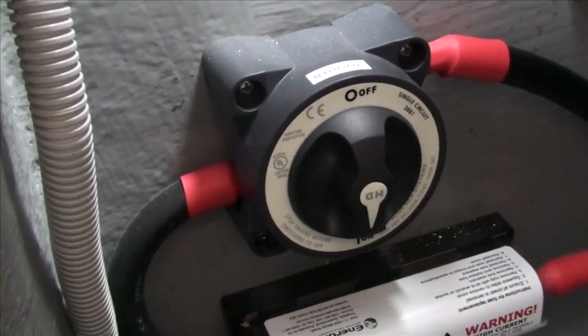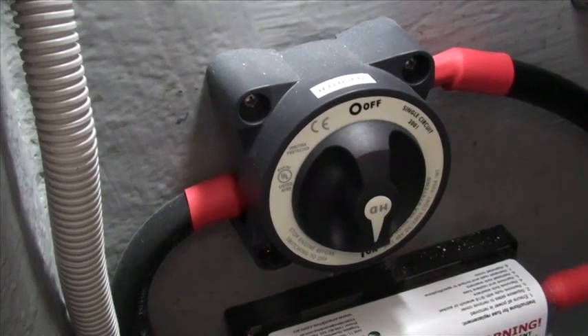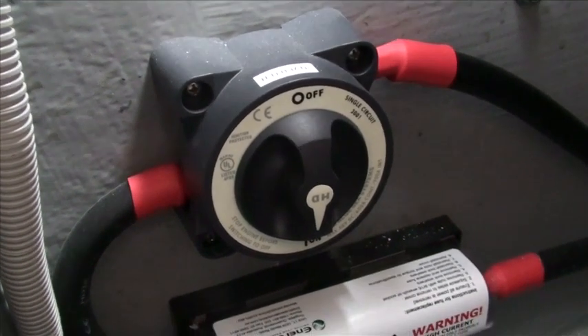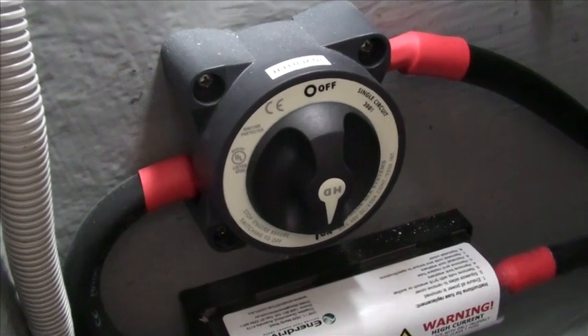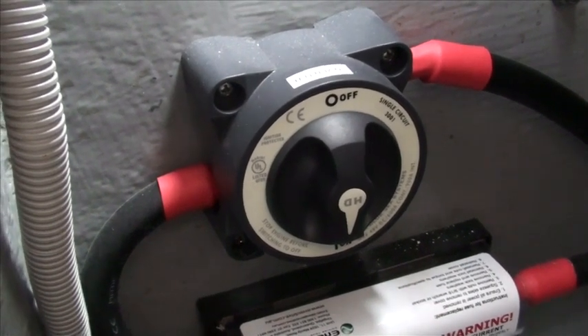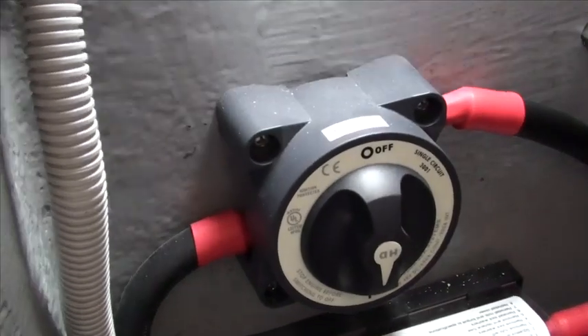Once again, if you're doing any sort of maintenance on the inverter or any electrical work, you want to be isolating the supply of 240 volt. The inverter, that's the only thing it's doing. The inverter supply is not going through any of your other isolator switches down there. The reason is you may want to turn off your house and leave your charger running, so that way your batteries will be maintained. If you turn off the house isolator, you'll still have charge supply going to the batteries.